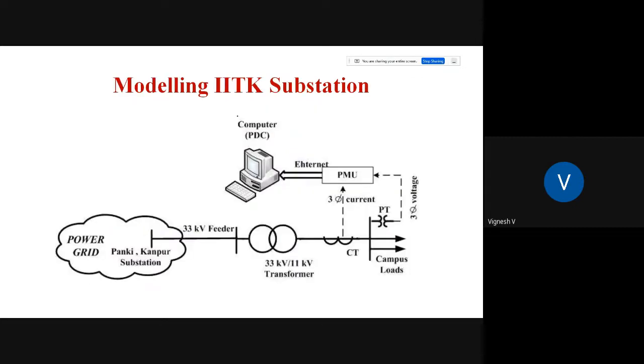Next slide. In this case, we are going to go one step ahead and model the entire IIT Kanpur campus load using the PMU data. The IIT Kanpur campus was deriving its power from a 33 kV feeder, and we had a 33 by 11 kV substation, where we installed the PMU on the 11 kV side, along with CTs and PTs.